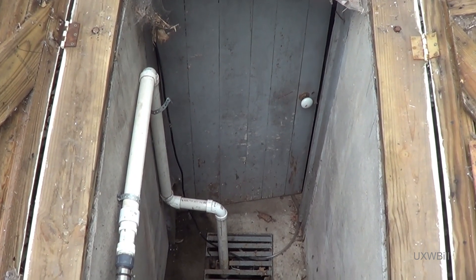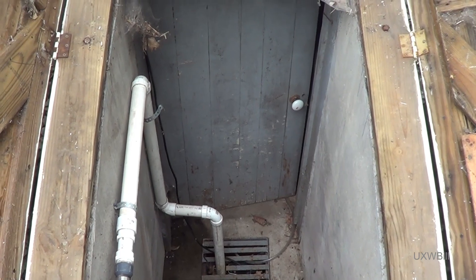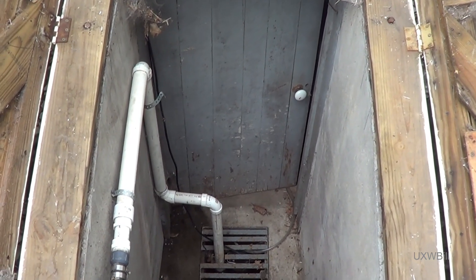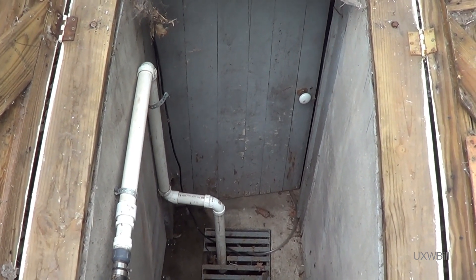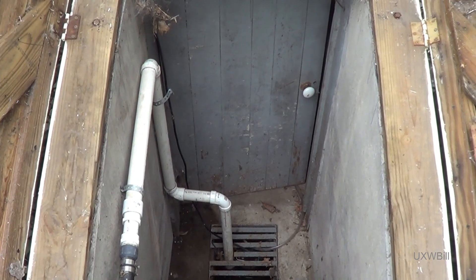What we're going to do today is take a look at a Trane 92% efficient furnace, 80,000 BTU heating capacity from 2003. This is in a house that was abandoned — and that becomes important later. I believe the problem with this has to do with the gas valve being bad, and we'll elaborate on that in just a bit.